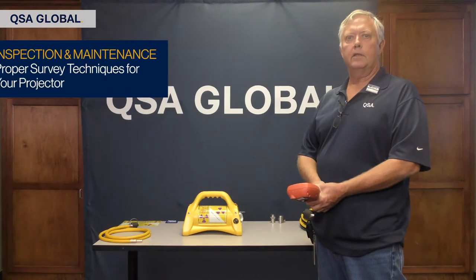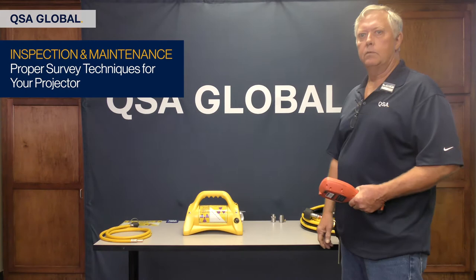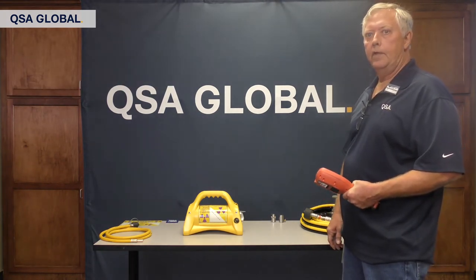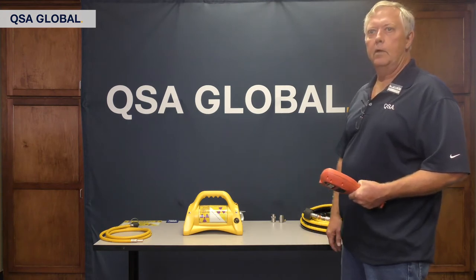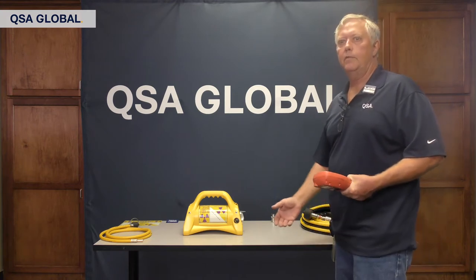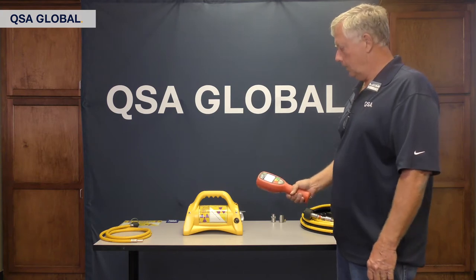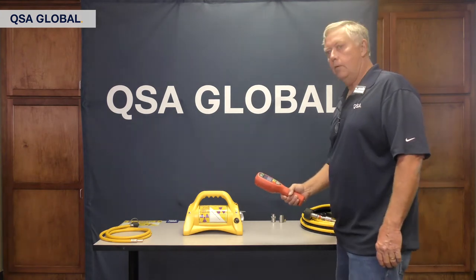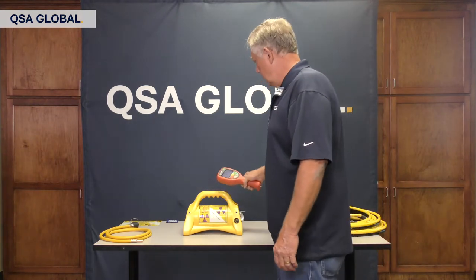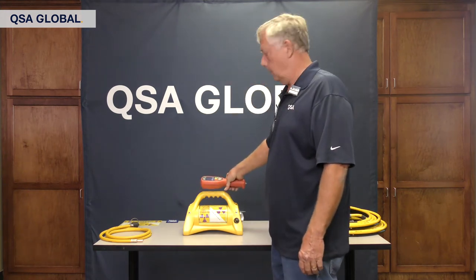I would like to talk to you about the proper survey techniques for a projector that you just received, be it coming in through your transport, FedEx, or what have you, or maybe just coming off the rig onto a job site. You always have to perform an initial survey prior to start of work. I have a Tracerco T402 meter here, and what I want to check for on all sides is that the projector is less than 200 mR per hour on the surface.